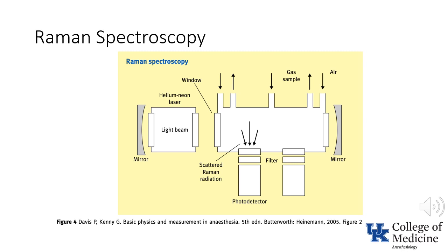Raman scattering is primarily of historical interest and was performed using a monitor known as the RASCAL. It was capable of measuring volatile anesthetic agents as well as respiratory gases. Raman spectroscopy relies on the fact that molecules absorb electromagnetic radiation and then re-emit that radiation at a lower wavelength; different molecules have different impacts on the wavelength. When using the Raman effect, a laser was passed through the gas sample, and by using filters unique for each gas, the concentration of CO2, oxygen, nitrous oxide, and volatile anesthetic agents could be rapidly measured. Although neither Raman scattering nor mass spectrometry are currently used, both offered the advantage of being able to detect nitrogen, making them ideal for detecting air embolism.